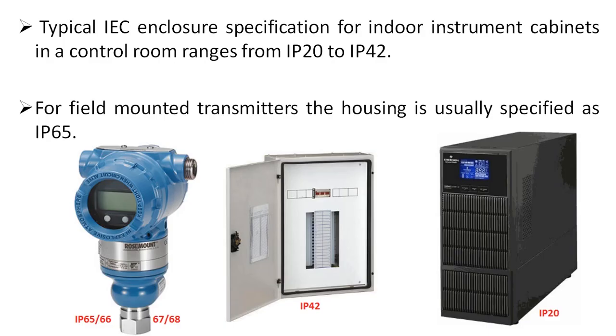Typical IEC enclosure specifications for indoor instrument cabinets in a control room range from IP20 to IP42. For field-mount transmitters, the housing is usually specified as IP65, because it is in an outdoor atmosphere where there is a chance of water spillage. For outdoor applications, IP65 or above rated transmitters are to be used. Here you can see a control panel with an IP42 rating, and a UPS located in the control room with an IP20 rating — meaning it has no protection against water spillage, so care should be taken while using this type of equipment in water spillage areas.